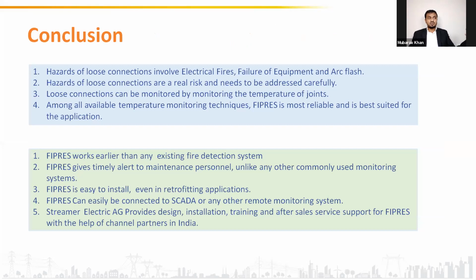Just to conclude, the hazards of loose connections involve electrical fires, failures, and arc flash. These hazards are real risks and need to be addressed very carefully. Loose connections can be monitored by monitoring the temperature of the joints. Among all available temperature monitoring techniques, FIPRES is the most reliable and best suited for the application. FIPRES works earlier than any existing fire detection system.